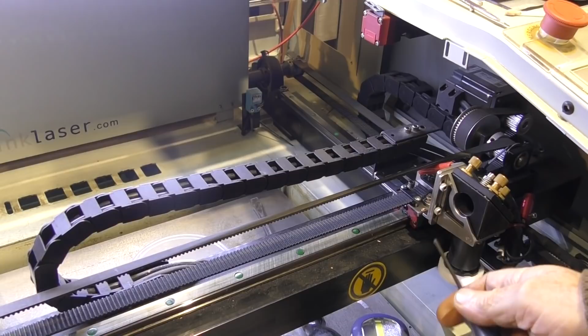The dots coincided, but they weren't on centre, so I was able to move the head to catch the beam in the right place. If I didn't have that ability on this machine, I would have to go all the way back to the tube and move the tube around. It's just like snooker or billiards or pool. You know, you're going to bounce off of 2 cushions and get to here. If you mess around with one of them, you mess around with the whole lot. So you've got to go back and reset the whole of the beam again.